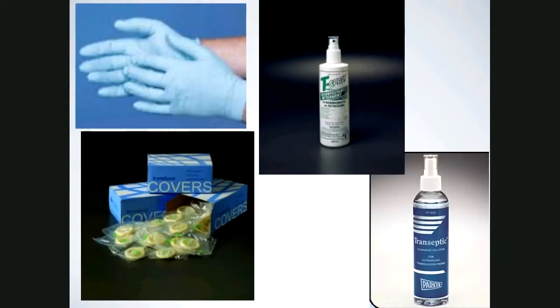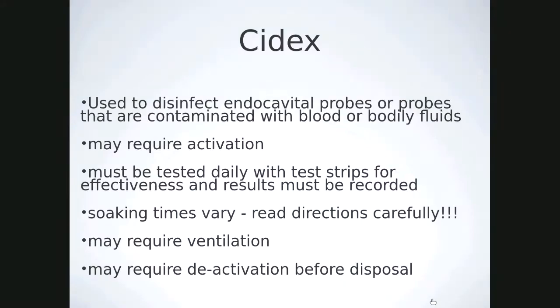Cidex is a disinfectant — some places still soak the probe that has been contaminated with blood or fluids. Most disinfectants like Cidex require that you activate them first, and they also have an expiration date. They must be tested daily with test strips to make sure they're still effective. Soaking times vary depending on the disinfectant being used. Read the container carefully — Cidex requires ventilation due to its strong odor and may require deactivation before disposal.